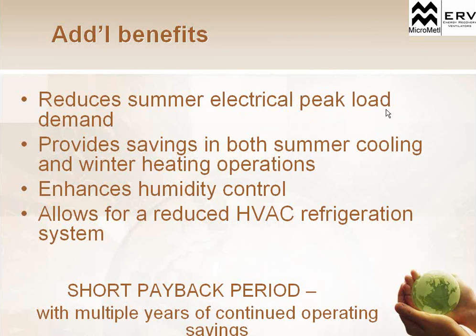So during the hottest portion of the day, we're using the energy recovery unit to pre-cool that air, taking some of the load off the HVAC system and off the electrical system. We're providing savings, like I said, in all seasons, both summer and winter, preheating and pre-cooling. And it's going to enhance that humidity control. I mentioned that during the summer, it's going to keep the humidity out of the space, and during the winter, it's going to help maintain humidity in the space. So you're not going to take that nice 40% relative humidity inside your space and send it outside. You're actually going to keep that inside the space.